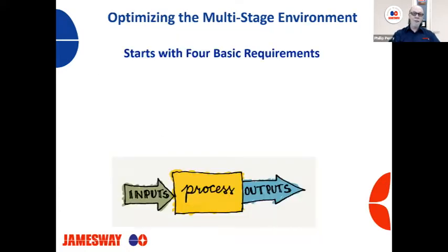So there are four basic requirements to these inputs. The first being electricity. You should have good, stable electricity. The components work off electricity. Your RTD probes and humidity probes work off of electrical values, and a lot of these values are to the 4th and 5th decimal point.